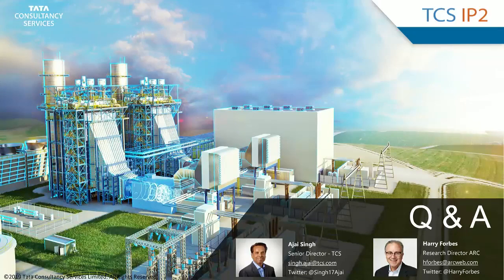From experience using these models, utilities have found that roughly four-fifths of situations identified as anomalies are caused by things like sensor failures. The analytics need to distinguish between that and something more important, like an analysis showing rotating equipment as overstressed. So a common garden-variety anomaly is probably just a sensor failure — an issue maintenance should address quickly, but it doesn't threaten equipment performance or capital equipment. These kinds of responses need to be integrated into the operation and maintenance procedures the staff uses.